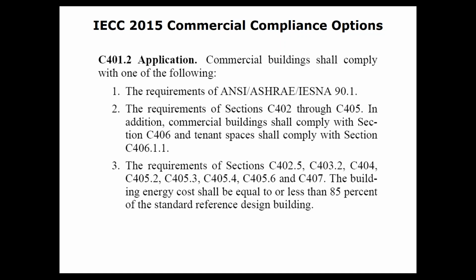The third method would be, well, I don't want to use ASHRAE, but I can't really do the prescriptive thing because I have some weird quirky things going on that don't work well with prescriptive. For example, if you have a VRF project, how the heck are you going to do the economizers? So in that case, you can use option number 3, which says you need to energy model the whole project, see how much energy it would use, then energy model as if you built it to code. Then energy model it the way you want to build it. And if the way you're going to build it saves 15% more energy than the way the code book had it, then you can do it your way. In Wisconsin, there's an amendment to that, and you do not have to do 15% better. You just have to meet the code. So you energy model it per the code, and energy model it the way you want to do it. And if you are equal or better efficiency, you're good in Wisconsin. In Illinois, you have to beat it by 15%.